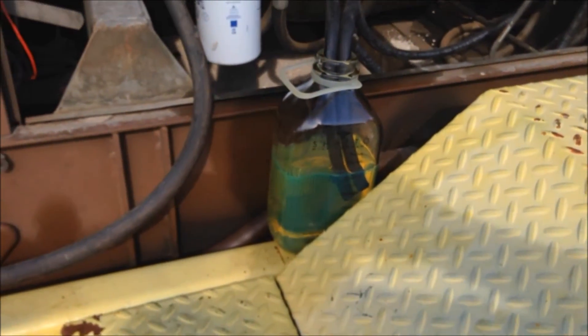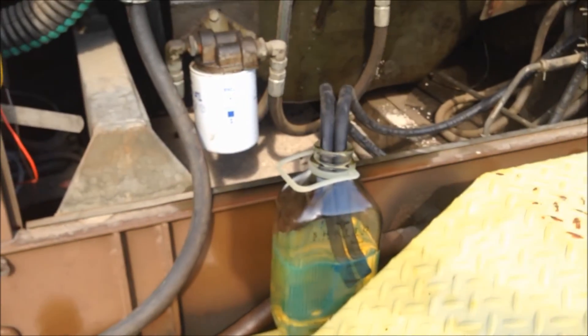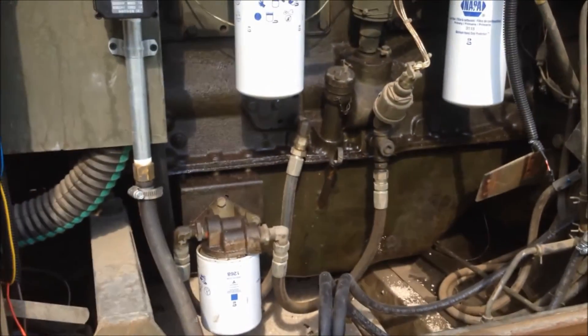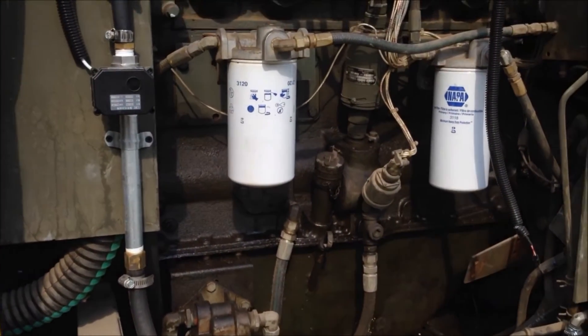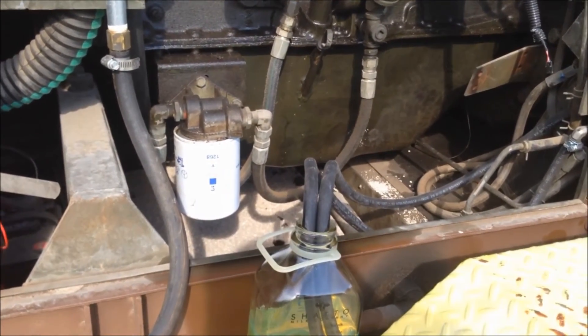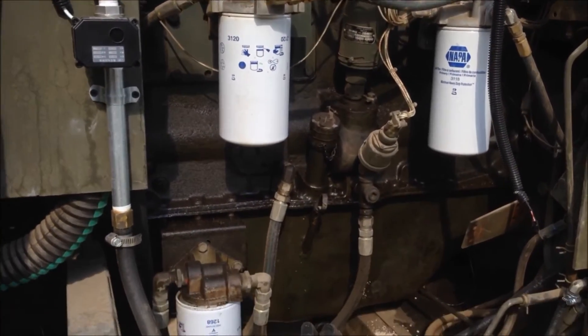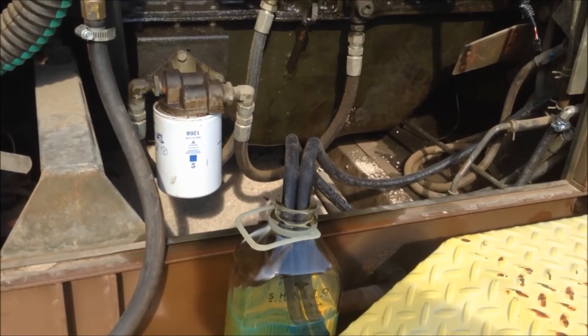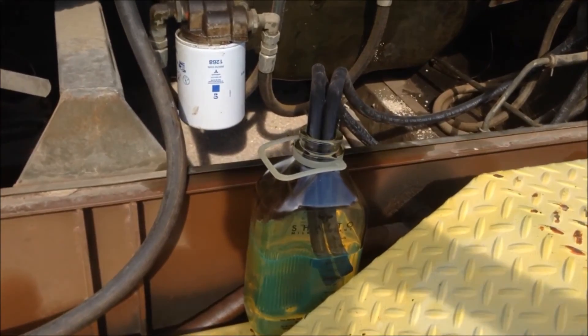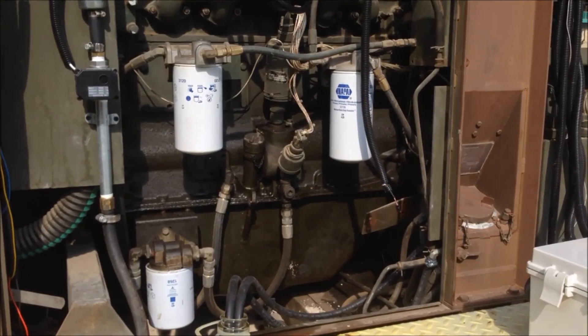So between the two fuels it looks like we used about half as much diesel on this run as we did diesel alone. We're set at about a 50/50 mix ratio here. We're kind of limited as to the pressure we get here from the local gas company to get enough pressure to actually run. This is such a big generator — 30 kilowatts — that it takes a little bit higher service pressure to hit the 70/30 ratio. But 50/50, hey, I'm happy with that. That's a good ratio.